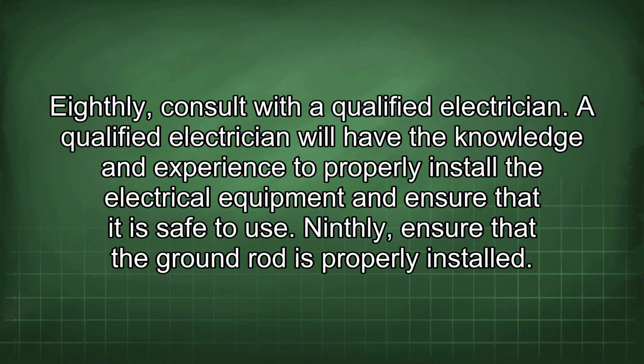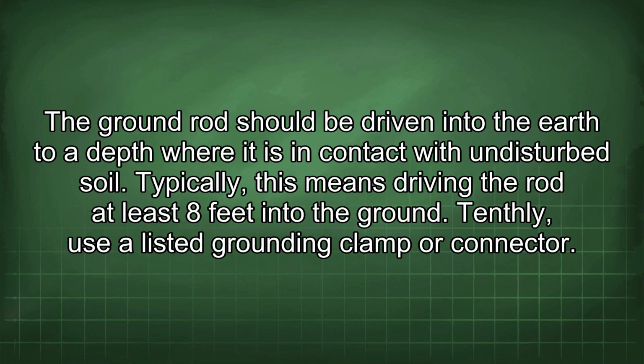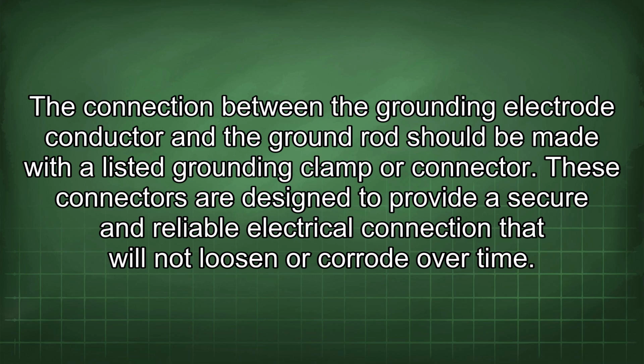A qualified electrician will have the knowledge and experience to properly install the electrical equipment and ensure that it is safe to use. Ninthly, ensure that the ground rod is properly installed. The ground rod should be driven into the earth to a depth where it is in contact with undisturbed soil. Typically, this means driving the rod at least 8 feet into the ground. Tenthly, use a listed grounding clamp or connector. The connection between the grounding electrode conductor and the ground rod should be made with a listed grounding clamp or connector. These connectors are designed to provide a secure and reliable electrical connection that will not loosen or corrode over time.